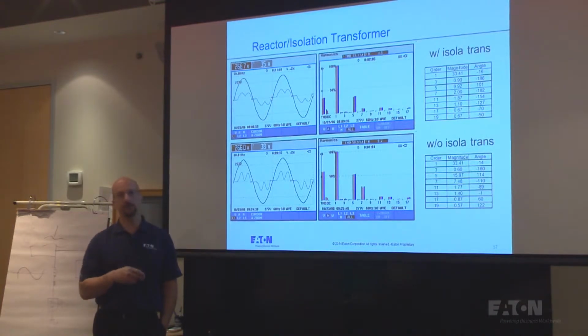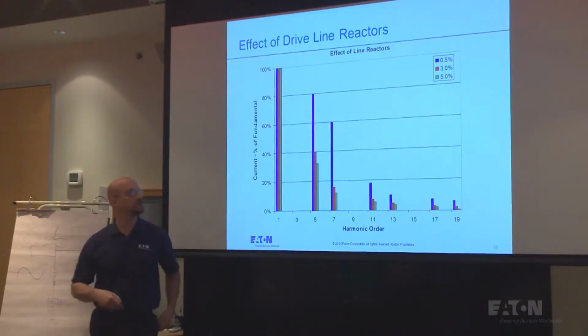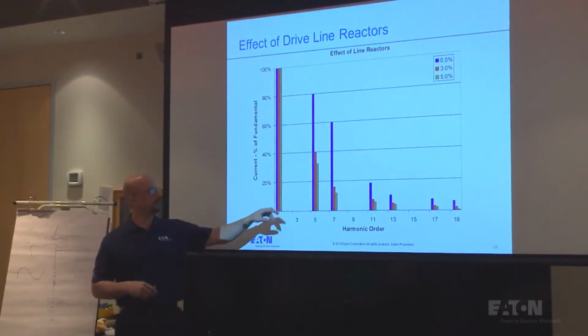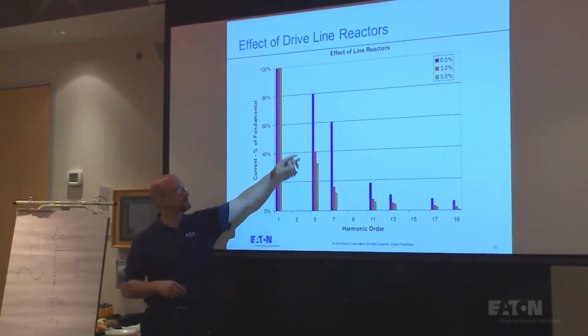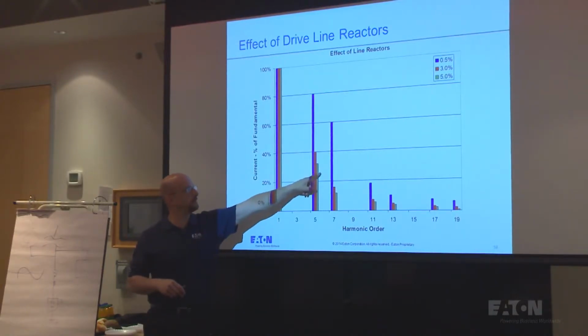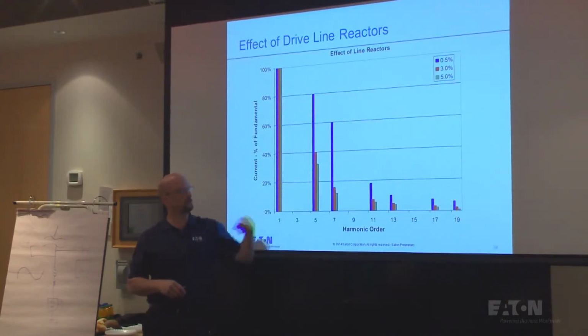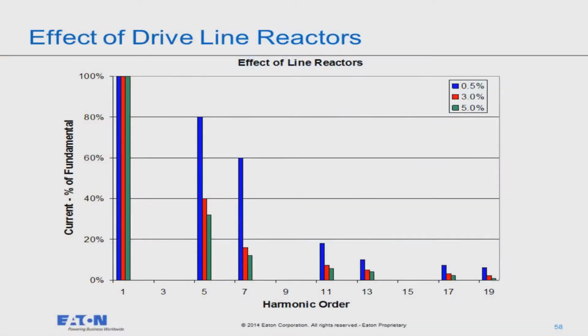A lot of people use drive isolation transformers, and that's the benefit of it initially. Plus you can do phase shifting with it as well. Here's the other graph that Adrian showed, and what this shows is you kind of get diminishing returns. So as you go up in impedance, the next level here, 8%, 10%, you're not going to get as much out of that reactor as you go up in impedance. So 3 to 5% is perfectly fine and going to work well in the power system.